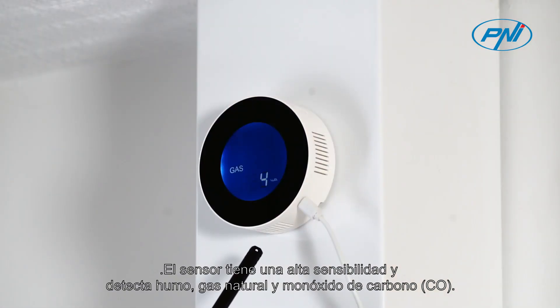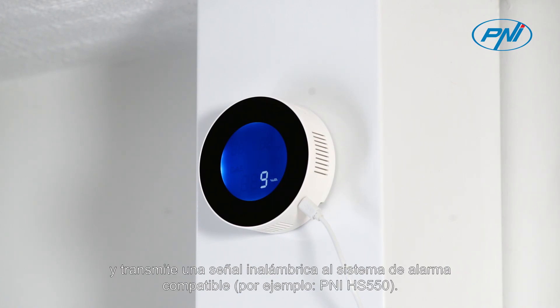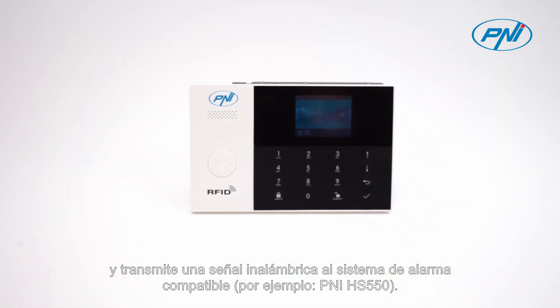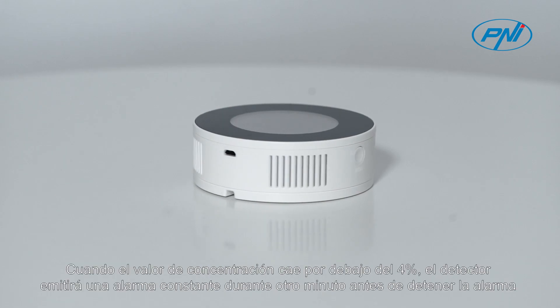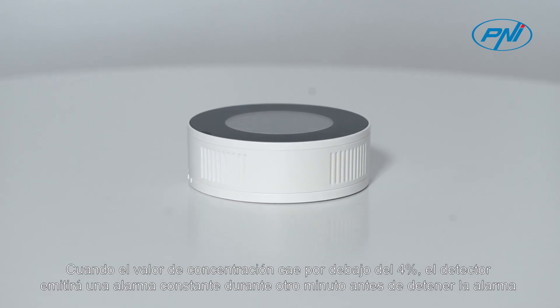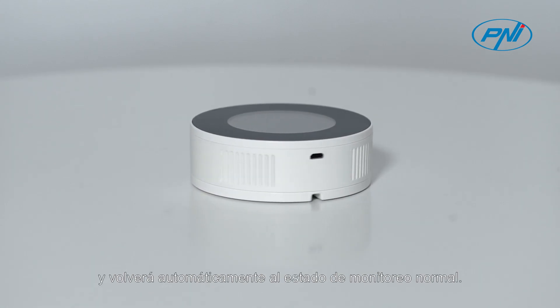When the ambient gas concentration reaches 8% LEL, the detector emits an alarm sound and transmits a wireless signal to a compatible alarm system, for example the PNI HS550. When the concentration drops below 4%, the detector will continue to alarm for another minute before stopping and automatically returning to normal monitoring state.